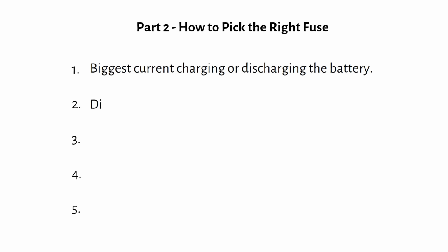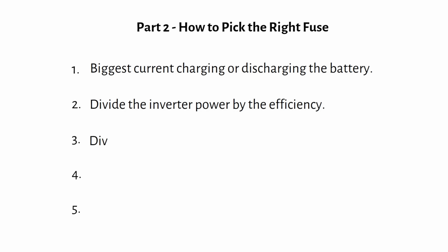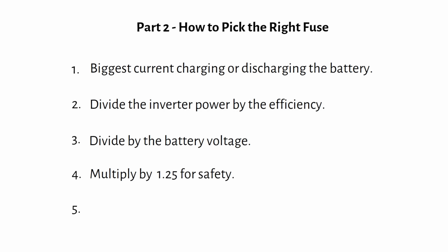The second step is to take the inverter power and then divide by the inverter efficiency. If you don't know the exact number, use 0.9. That gives you the real DC power being pulled out of the battery. The third step is to divide that by your battery voltage. Now you have the battery current in amps. Then we multiply the current by 1.25 for safety. And the last step is to pick the closest fuse size up from that number.